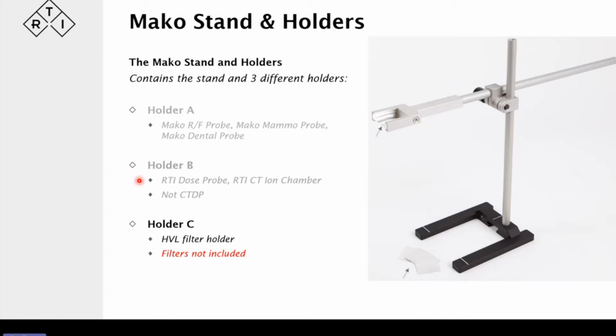You can then do your traditional HVL measurement. If you look here at the base of the stand, you may make out there is a slot here for the probe, the Mammo or the RF probe, to slide in facing up, and the detector will align perfectly along these lines. Where this line and this line intersect, that's where the detector will be. So if you want to do the HVL measurement, that's where you place the probe, align it, and then put the filters in as needed.